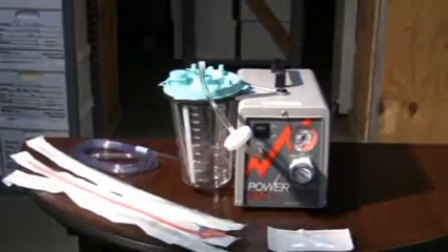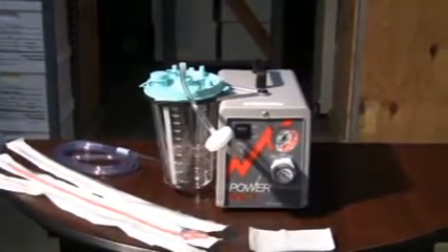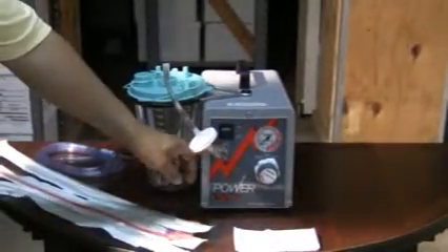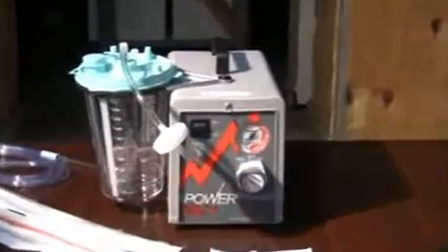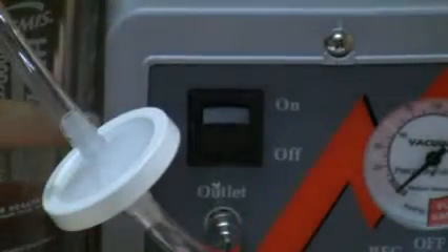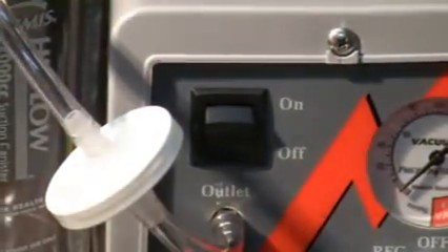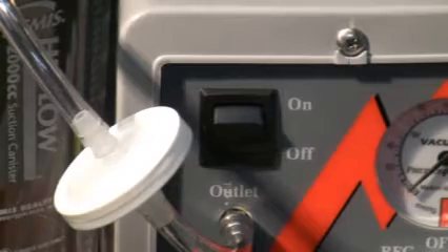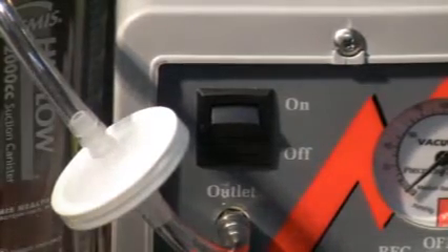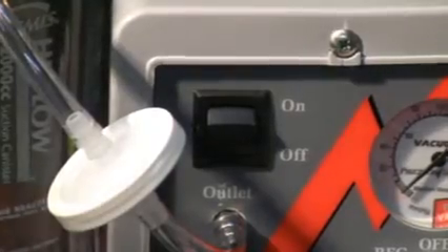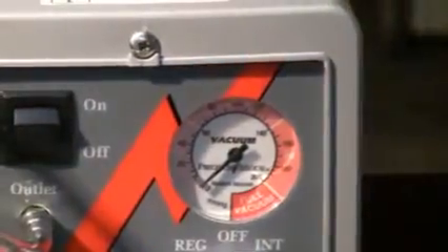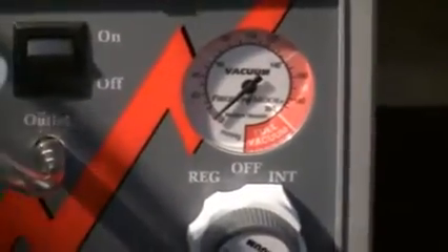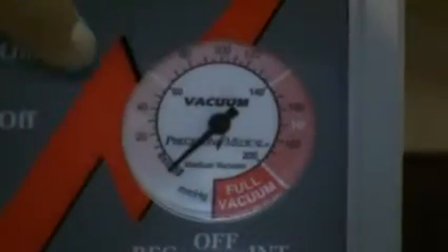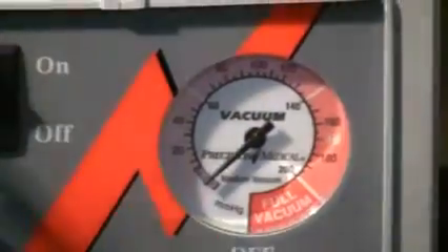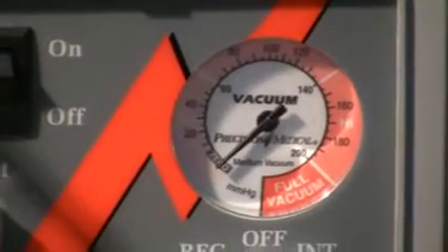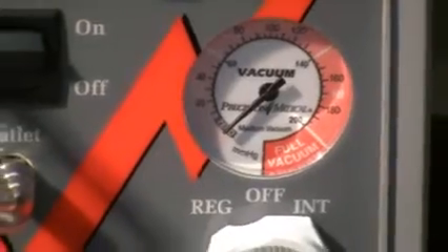Before we proceed to connect our tubing to the suction canister lid, we will continue on with the features of your suction machine. Directly located above the outlet of the intermittent suction machine is your on and off power switch. When your suction machine is not in use, it should always be placed in the off position. It should only be placed in the on position during suction procedures. To the right of your on and off switch, you do show your vacuum gauge. Your vacuum gauge can go preset up to 200 millimeters of mercury for vacuum.